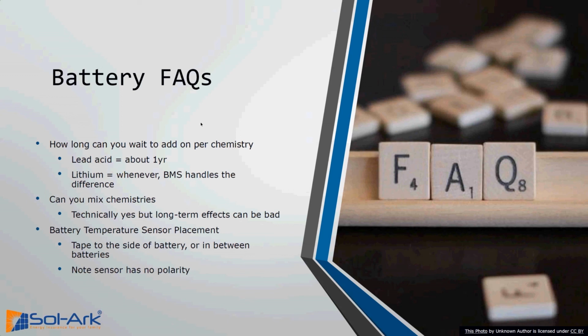Also, a quick note on the temperature sensor placement. Usually what we recommend is you just tape that to the inside or in between a few batteries in the battery bank, and that gets good contact with the thermal mass of the batteries. Whenever you're hooking the battery sensor up to the Sol-Ark, it goes in pins 1 and 2. Don't worry, we have diagrams in the manual for finding that. It's also labeled on the circuit board, but there's no polarity on that, so don't worry about the red and white wires. Just go ahead and stick it in there.